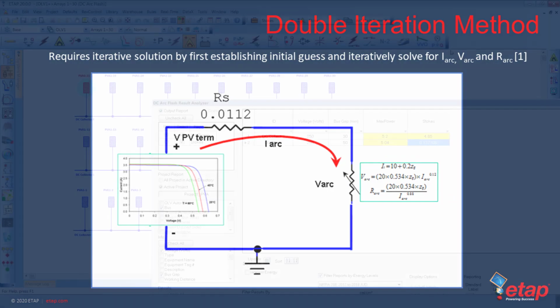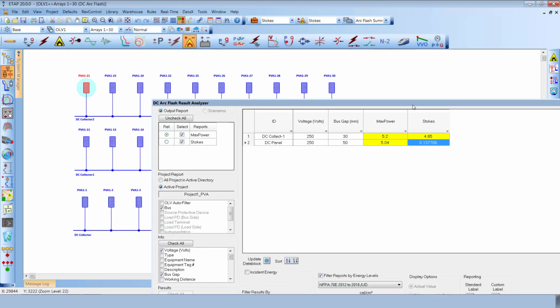And it is for the same reason the max power method for higher voltages could give you a very high incident energy, or in lower voltages could give a very low arcing current that causes a higher incident energy due to a longer clearing time. Whereas the Stokes method with the double iterative technique would be more useful in giving the right estimate of the incident energy compared to the maximum power method.